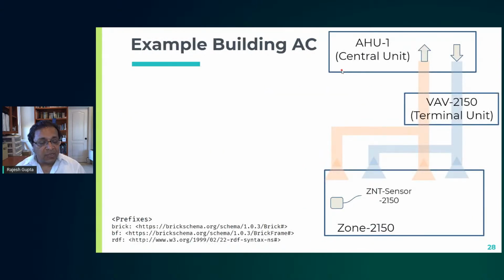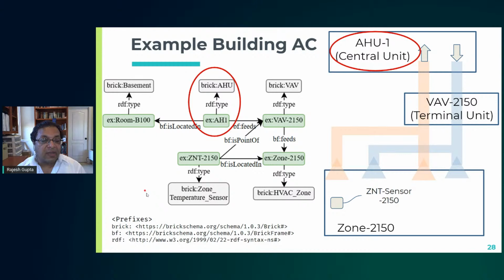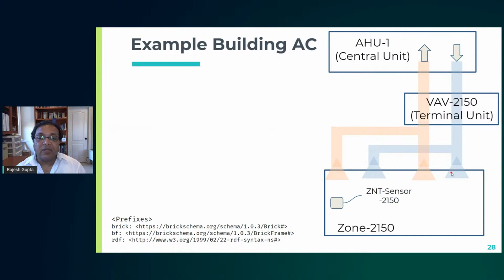All right. So let me now start to walk you through examples. I told you about the namespaces I'm using, and they're using Brick prefixes, but basically you have Brick, which refers to the Brick schema. I think this might be deprecated, it might be a BrickFrame schema, and then you have RDF, for example, from W3C.